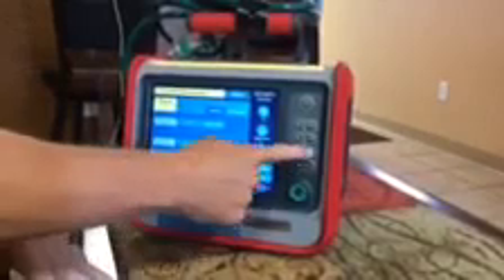But what's neat is when you engage the nebulizer function here, there's a side port over here that you connect your nebulizer to, and the machine will only deliver the nebulizer during inhalation, which allows the patient to only get the nebulization during inhalation, and they get all the medicine, which is pretty cool. You have an alarm silence button here that will silence your vent for 2 minutes. And the way that this ventilator works is it's a push, turn to whatever you want, and confirm. So it's a push, turn, and confirm ventilator.